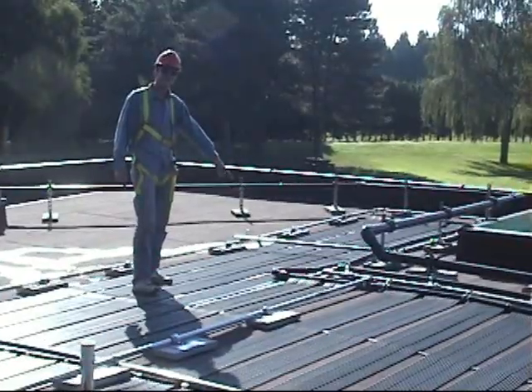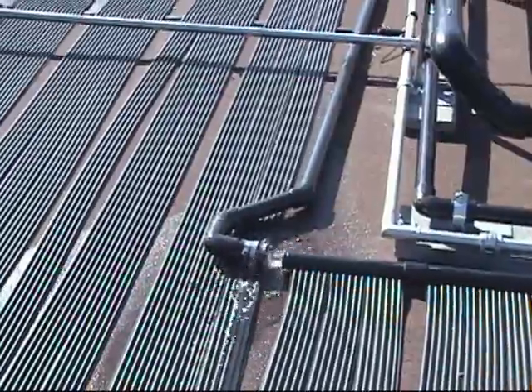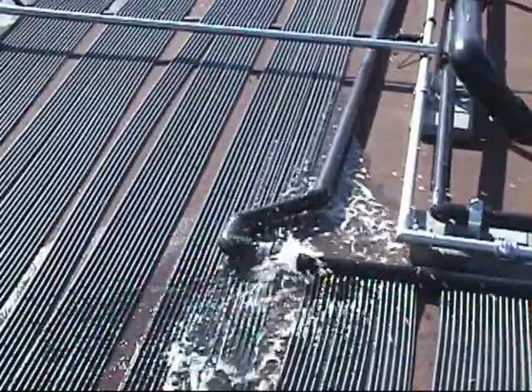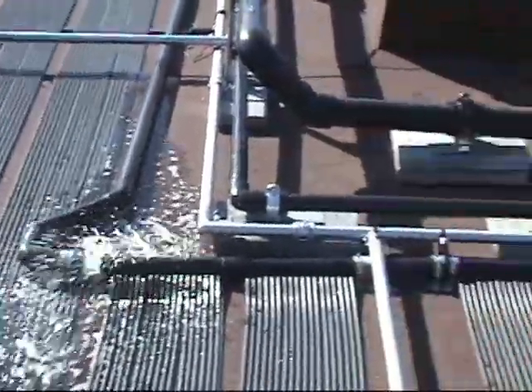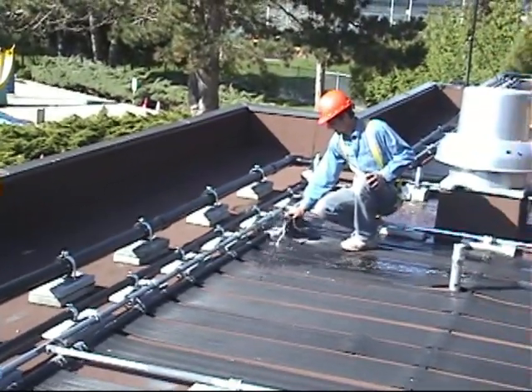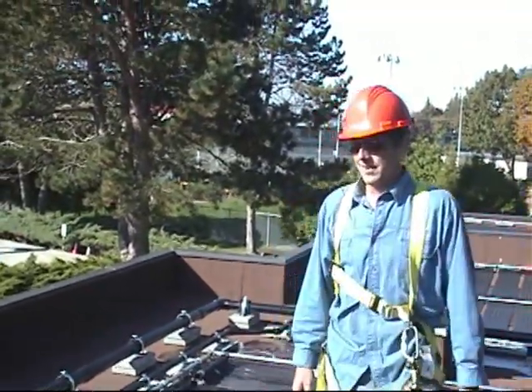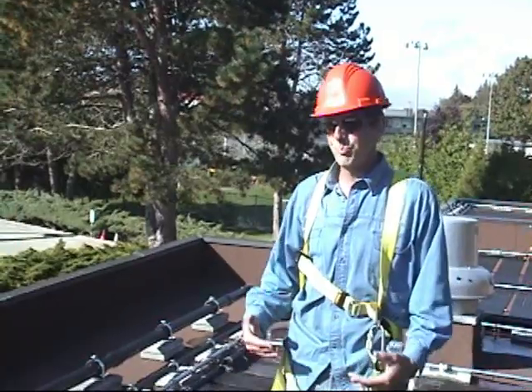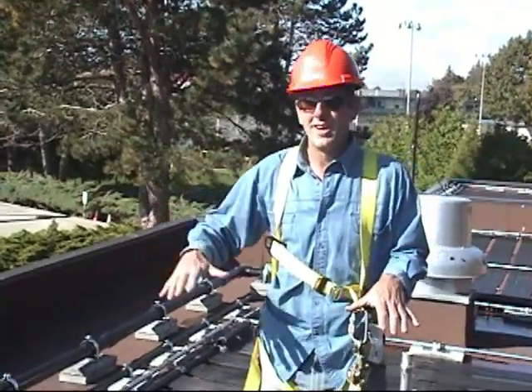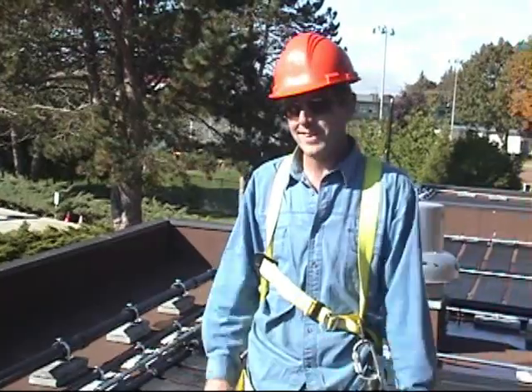Water's going to come out right here. It really works. The shop vac creates a slight pressure drop through the system — maybe a psi — which means it'll actually raise water as much as a foot or two to account for the elevation difference. So it'll force water out of tubes that are sitting in the middle of this bank.